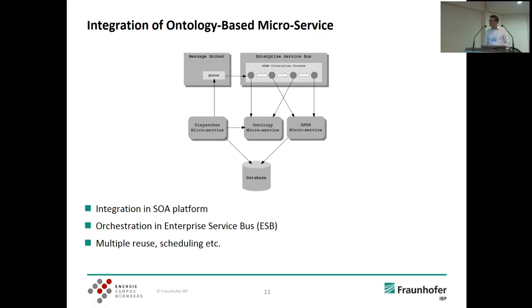So how is this then integrated? Or, the microservice I showed earlier, how do we integrate this in this platform? To be specific, the microservice I just mentioned down here is an APAR microservice. And we also have the ontology microservice, which holds the triple store. It can be accessed by some API. The dispatcher microservice itself is only triggering the execution of the fault detection method. How this is running is defined in a process which is defined in the enterprise service bus. And the message broker we use allows further execution of several processes. So this can be scalable for multiple AHUs, depending on the hardware we're using.